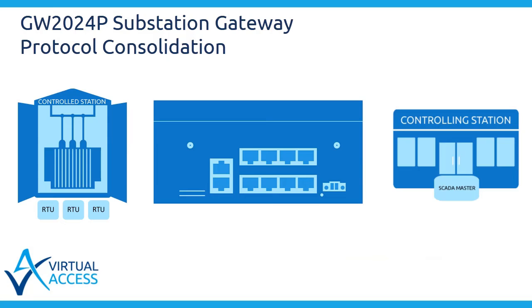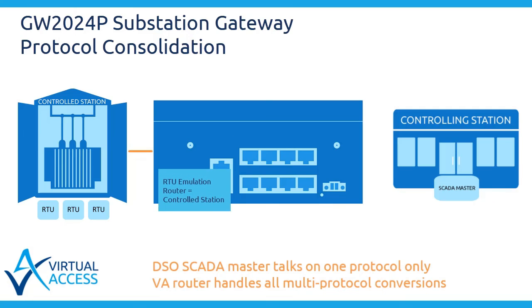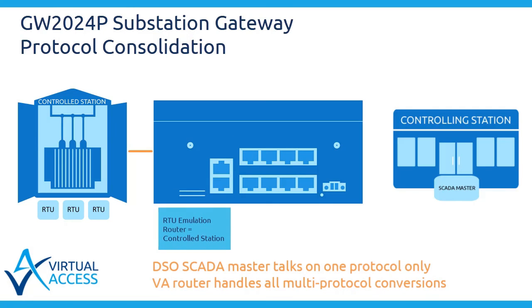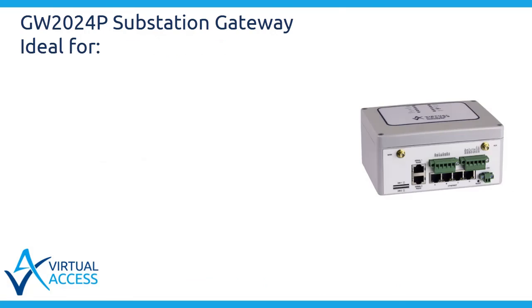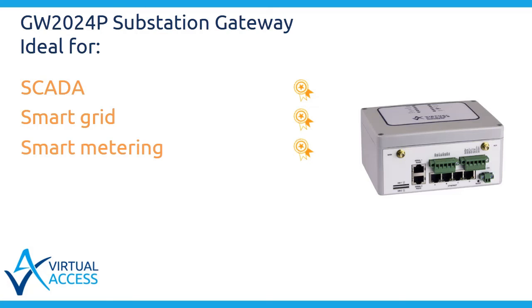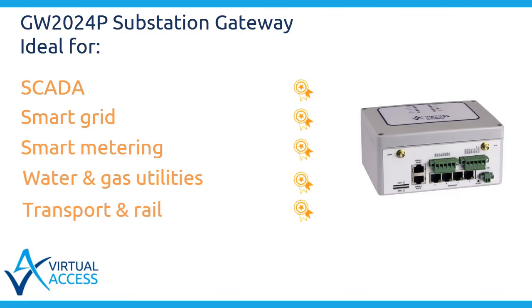For connection to the SCADA master, the GW2024P Substation Gateway emulates an RTU, which is the controlled station function. For connection to an RTU, it emulates a master, which is the controlling station function, and the data point mapper maps between the master and RTU protocols. The GW2024P Substation Gateway is ideal for SCADA, smart grid, smart metering, water and gas utilities, transport and rail.